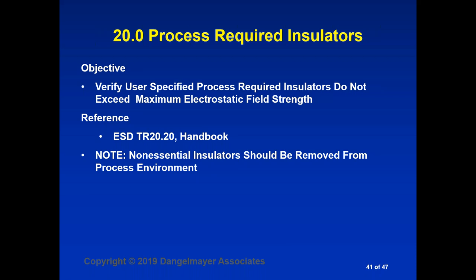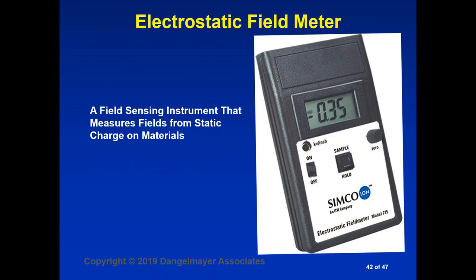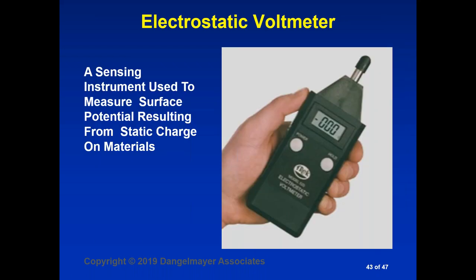And when we talked about non-essential insulators, S20.20 is very clear that non-essential insulators should just be removed from the process environment. But what do we do about our required insulators? Well, we need to make some charge measurements on them. The instruments we use are either an electrostatic field meter. This is an example of one of them. We might also use an electrostatic voltmeter.